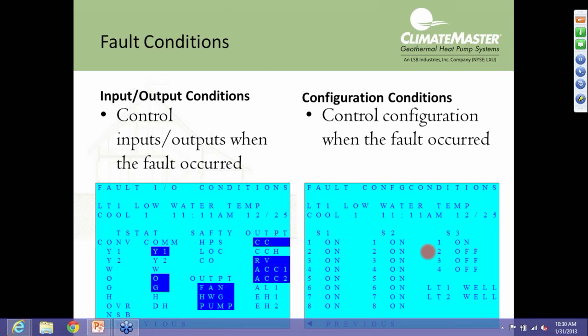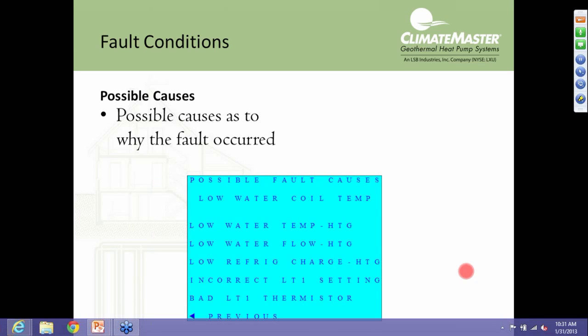This could be helpful, again, if we got somebody maybe playing around with the unit that shouldn't be, maybe made a movement on a dip switch, had it lock out, then oh, they moved it back. This will show at the time of the fault what position those dip switches were in, as well as the jumper, LT1. And then possible causes. So again, this LT1 fault, low water temp in the heating mode, low water flow heating, and so forth.